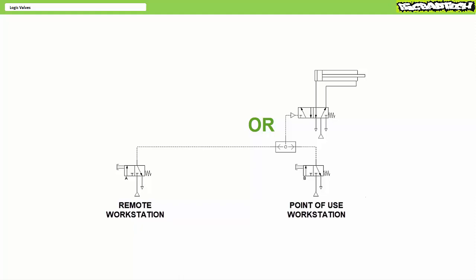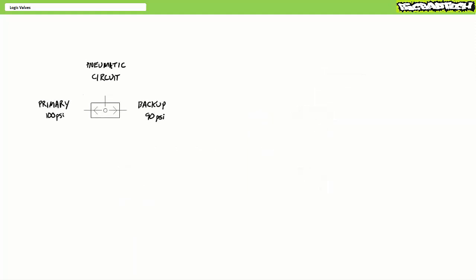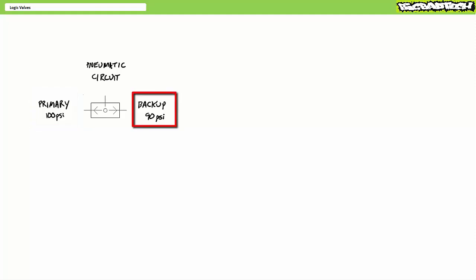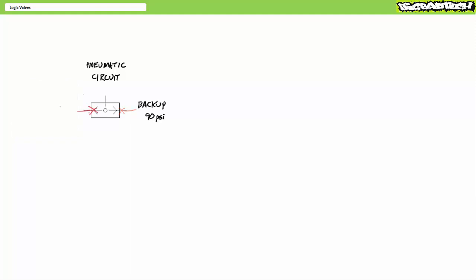Beyond logical operations, the pressure selection feature of the OR valve is quite a handy feature commonly employed in pneumatic systems necessitating a backup or alternative source. Consider a primary pneumatic source operating at 100 PSI and a backup accumulator charged at 90 PSI as inputs to an OR valve supplying some critical pneumatic system. In ordinary circumstances, the OR valve passes the primary source at 100 PSI and blocks the backup. In the event of failure or catastrophic pressure drop, the OR valve blocks the primary and passes the backup accumulator, allowing time for an orderly shutdown.